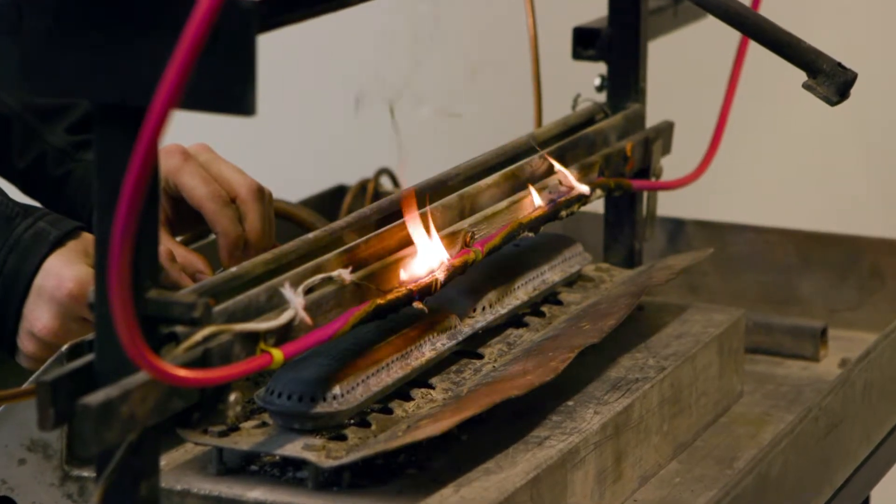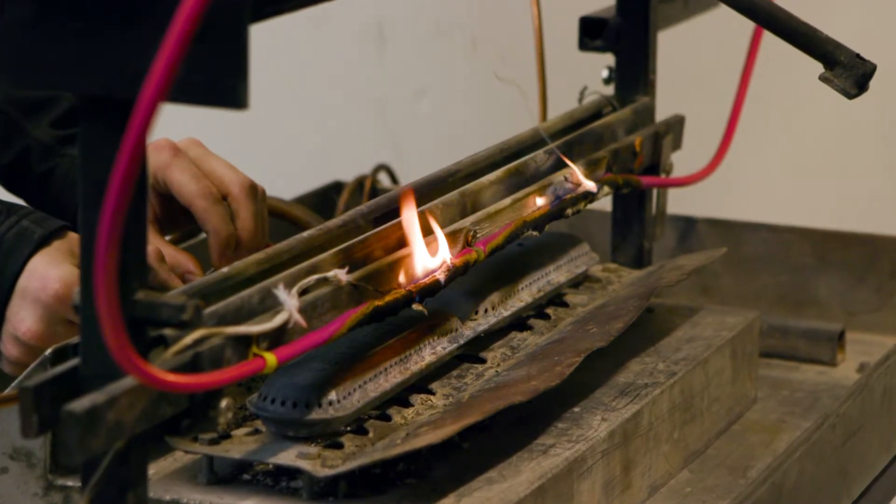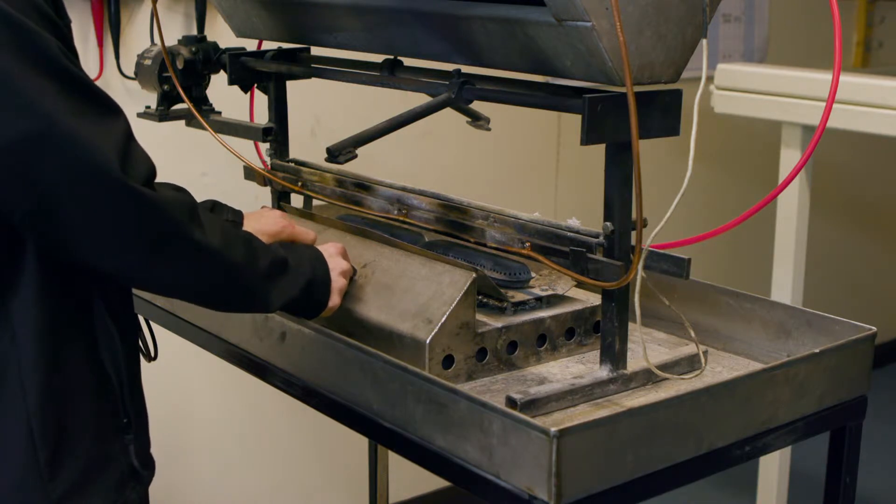You can see smoke and flames clearly coming from the fire resistant cable. It does not self-extinguish. In fact it actually reignites the gas when the burners are turned back on.